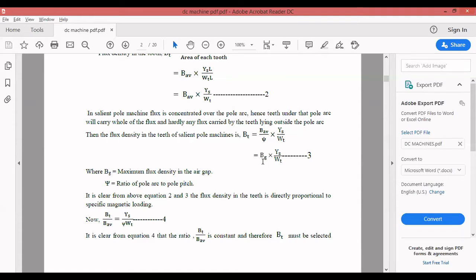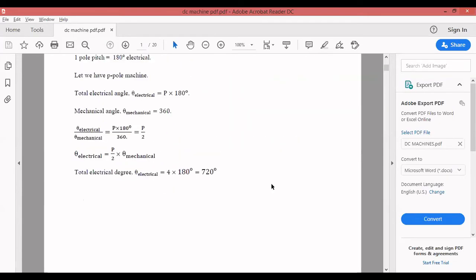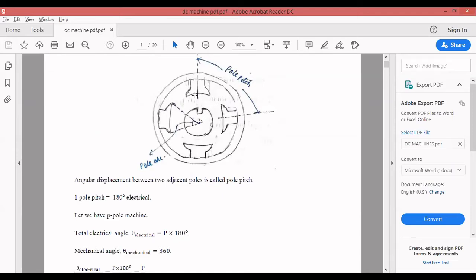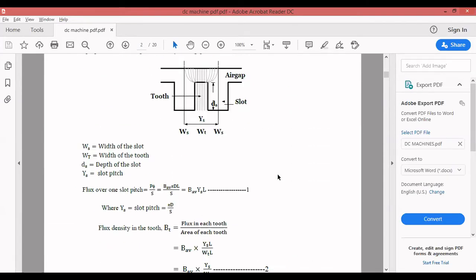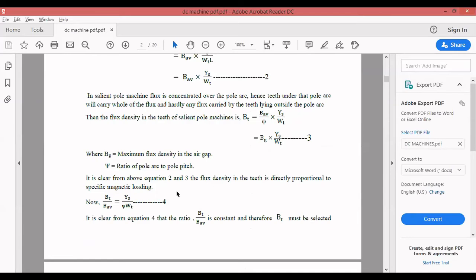It is clear from equations 2 and 3 that flux density in the teeth is directly proportional to specific magnetic loading. From equation 4, B_t / B_av = Y_s / (psi * W_t) is constant. Therefore B_t must be selected such that it does not exceed the maximum specified magnetic loading, which is 2 to 2.2 Wb per meter square for DC machines. The ratio should be maintained so that B_t does not exceed 2 to 2.2 Wb/m².